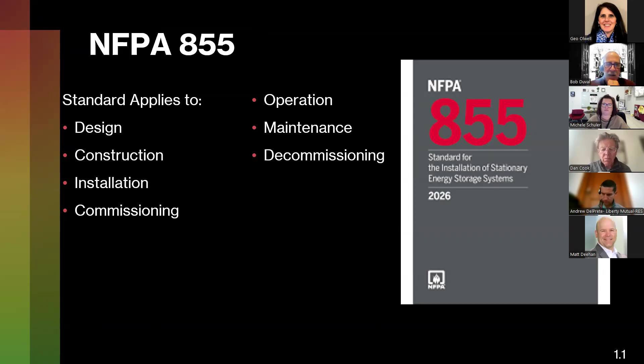So I mentioned 855, I'll get to that now. This is the latest edition, just out about a month ago — the third version of this document, the standard for installation of stationary energy storage systems. If one is installed or proposed in one of your facilities, it should mention 855 somewhere in the plans. This covers a BESS from cradle to grave: design and construction, installation, commissioning, operation, inspection testing and maintenance while in place, and decommissioning afterward. These things have a life — you plan them, install them, they serve their purpose, and then get decommissioned, either without a failure or after a battery failure.